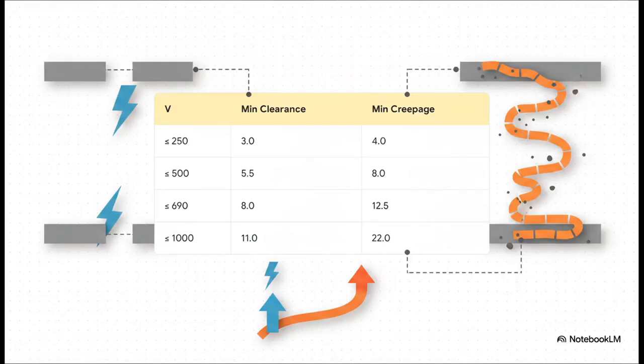Now, what's really fascinating here is how these numbers scale. Just look at these baseline values for a pollution degree 3 environment. Down at 250 volts, your clearance is 3 millimeters and your creepage is just slightly higher at 4. But scan down that table to 1,000 volts. Clearance requires an 11 millimeter gap, but creepage? It demands a massive 22 millimeter surface path. It literally doubles the clearance requirement. Creepage scales so much faster as voltage goes up. This proves exactly why you can't just set an air gap and assume your surface path is totally fine.